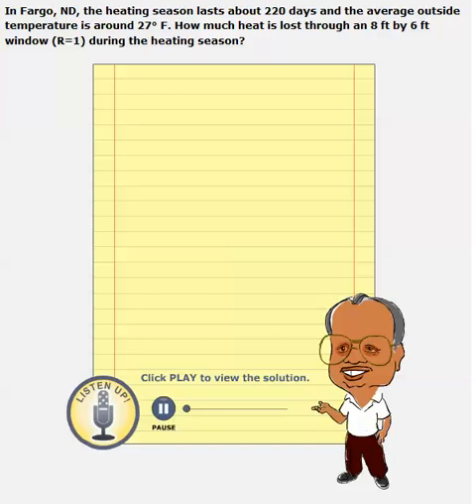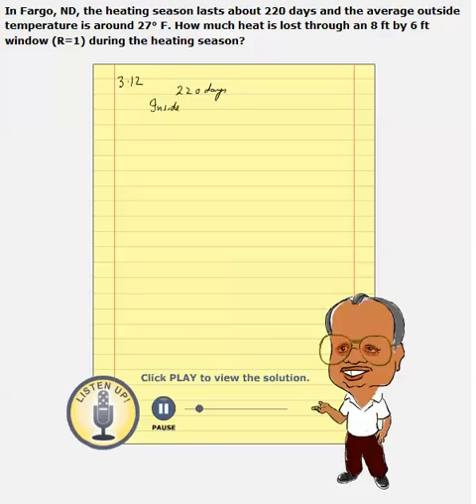This problem is very similar to the last one, 311. This problem 312 involves, again, heat loss through a season. We need to calculate the HDDs. The heating days are 220 days. The temperature difference is inside 65 degrees Fahrenheit, and outside the average temperature is 27 degrees Fahrenheit for all 220 days.